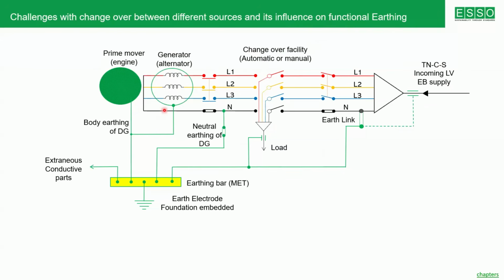The changeover is happening. Body of the generator is connected to a common bus bar. Neutral is also connected to the same common bus bar. Incoming earth is also connected to the same bus bar. Extraneous conductive parts are also bonded to the same bus bar. This is the recommended method of earthing for a changeover system.